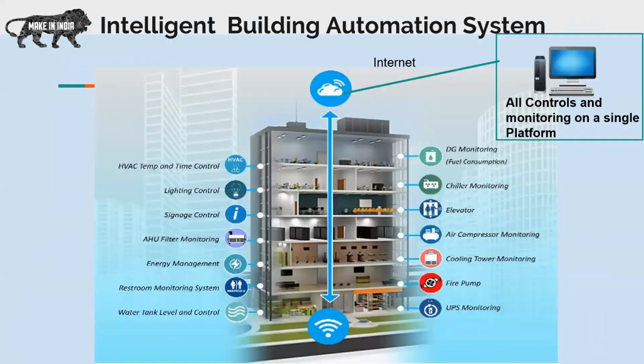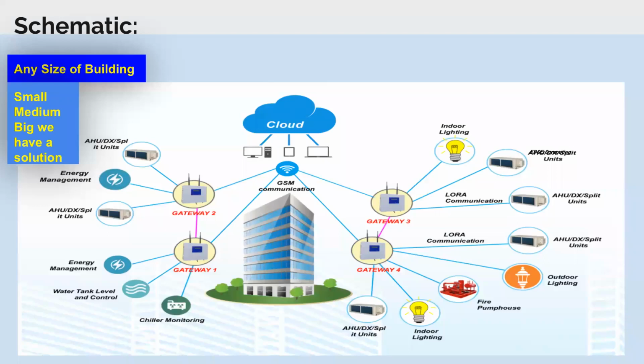So now coming to the building automation part, these are the limited set of parameters which we have shown here. The list is exhaustive. So the HVAC temperature and timing control, lighting control, signage control, AHU filter monitoring, energy management, restroom monitoring, water tank level and control, DG monitoring, chiller monitoring, elevator control, and many more. So coming to the schematics, when we go to a building, we identify the details which we are required to monitor and control, and we do a complete site survey of the building, and based on that we determine the number of communication points.